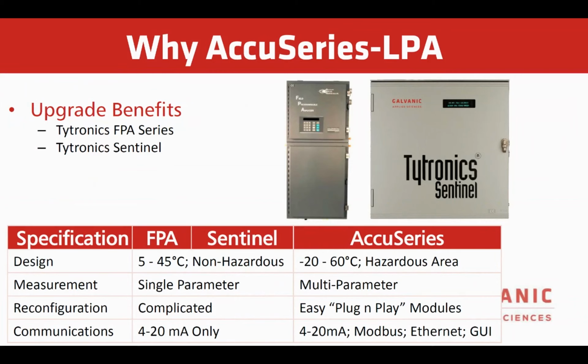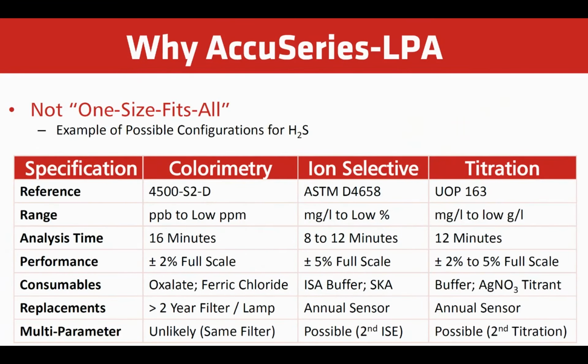The old analyzers were single parameter. We now offer multi-parameter. To reconfigure the older devices, it was quite complicated and a lot of parts and pieces, and it was almost easier to just purchase a new analyzer as opposed to the AccuSeries, where we can just really plug and play different modules and change the programming, and we're up and running to what's required. Communications was only 4 to 20 on the older devices. We still have 4 to 20, but we also now offer the Modbus, Ethernet, and Ethernet GUI. So for remote access to the device. Not one size fits all.